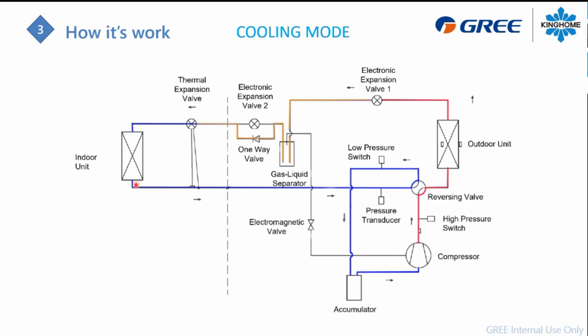After that, it will go back to the outdoor unit, flowing into that reversing valve, and then back into the accumulator. So you will hit another cylinder here. This accumulator will just protect the compressor from pumping liquid, because the compressor can only pump vapor. So this pipe going down here, you can have some liquid refrigerant in it, but this one just stops at the top of the accumulator. So you will just take the vapor refrigerant and compress it, and you will cycle it again.